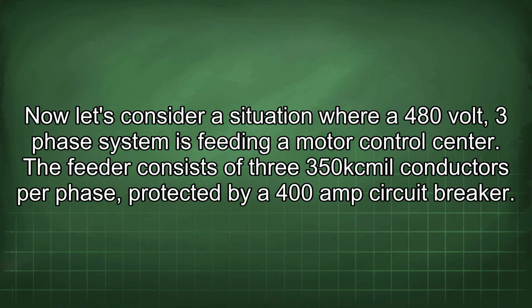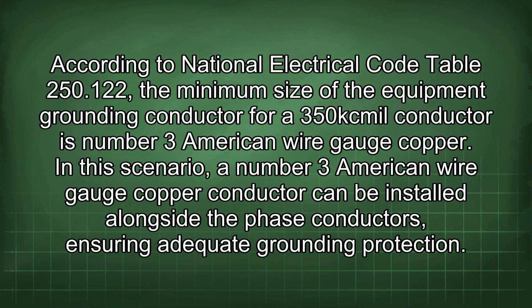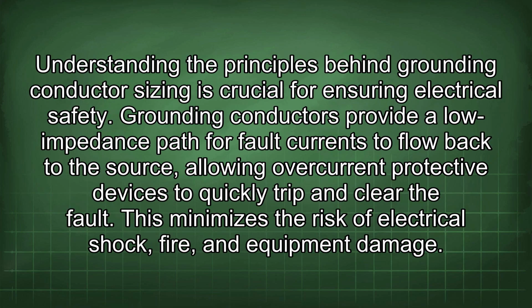Now let's consider a situation where a 480-volt, three-phase system is feeding a motor control center. The feeder consists of three 350 kcmil conductors per phase, protected by a 400 amp circuit breaker. According to National Electrical Code Table 250.122, the minimum size of the equipment grounding conductor for a 350 kcmil conductor is number 3 American wire gauge copper. In this scenario, a number 3 American wire gauge copper conductor can be installed alongside the phase conductors, ensuring adequate grounding protection.